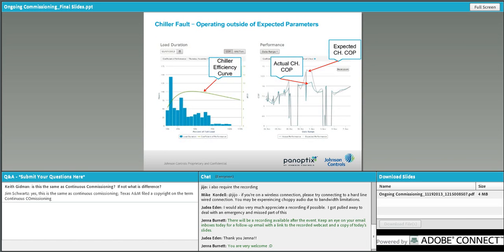Next, this is a more complex FDD. The shot on the left side of the screen is a chiller efficiency curve for a particular chiller. This is the actual chiller efficiency curve for a chiller at this site. That curve is used to establish the expected chiller performance, which is shown in COP, or coefficient of performance. COP is similar to looking at a car's miles per gallon. It's just the efficiency. The higher the miles per gallon, the more efficient the car is. With COP, the higher the COP, the more efficient the chiller is. You can see that the expected COP is over 12.5, and this particular chiller is running just over 10. So something is causing that reduction in performance.